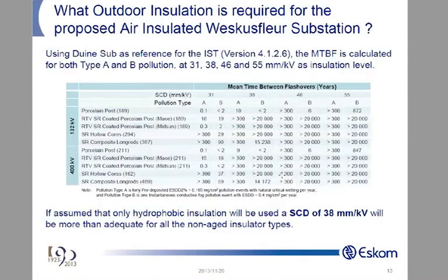And this here is how you should be using IEC 60815. So the concept would be to use 60815 correctly. Measure your environment, get your data. Look at your climate, get your data. Go and get a reference or a candidate and get candidate insulators. Have them evaluated, get their pollution performance curves. Take the two, go in, do the stats. From there, what voltage? Okay. What line performance do you expect?